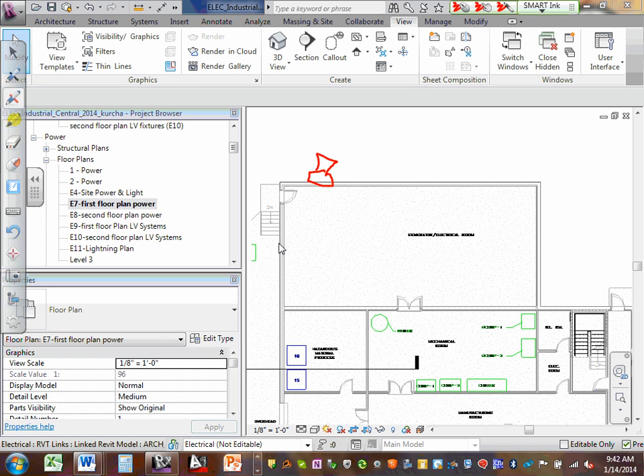So let's talk about flow switches and tamper switches, and exterior horn strobes for a minute. A sprinkler system has a switch in it called a flow switch. There can be multiple flow switches based on how that sprinkler system is zoned. Okay, in other words, you're providing sprinkler protection to various areas inside a building via what's called sprinkler zones.